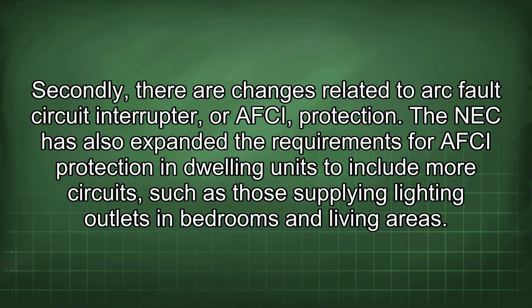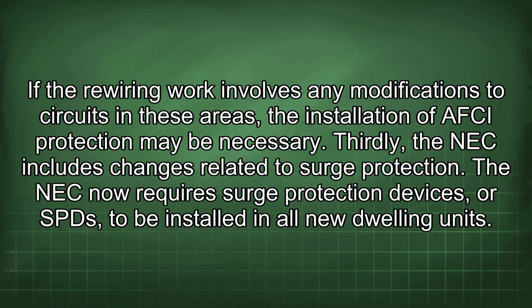Secondly, there are changes related to arc fault circuit interrupter, or AFCI protection. The NEC has also expanded the requirements for AFCI protection in dwelling units to include more circuits, such as those supplying lighting outlets in bedrooms and living areas. If the rewiring work involves any modifications to circuits in these areas, the installation of AFCI protection may be necessary.